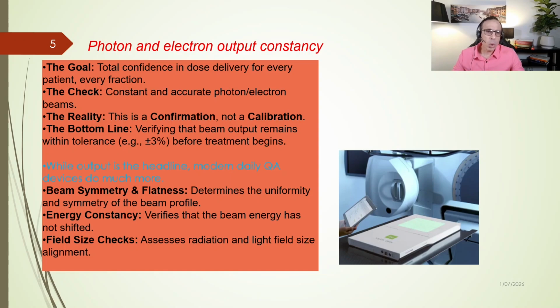When we talk about daily QA, our ultimate goal is simple: total confidence. We need to know with absolute certainty that we are delivering the correct dose to every patient during every single fraction. To achieve this, our primary check is the constancy and accuracy of our photon and electron beams. But there is an important distinction to remember here. This is a confirmation, not a calibration.